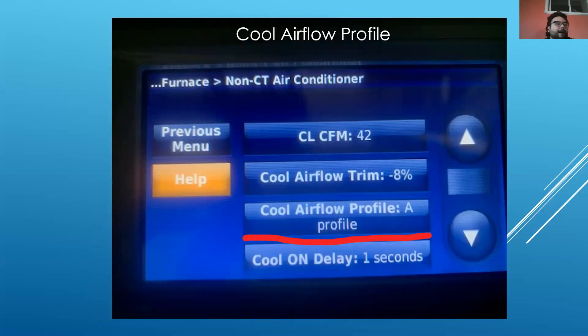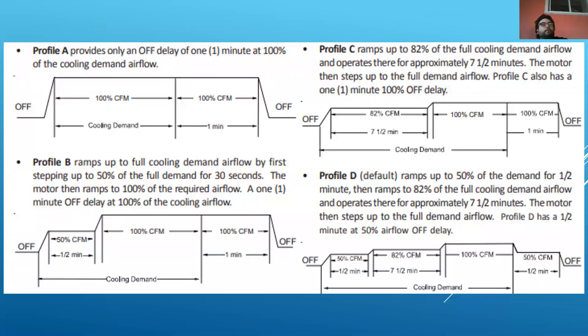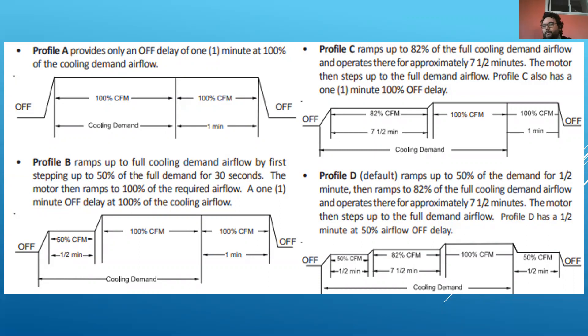We can also set profiles, which control the actual ramping up and down of the fan during a cooling call. Profile A ramps up to 100% of demand right away — no attempt to dehumidify with a lower fan speed. This might work for customers who want immediate airflow or for certain zoning systems. Profile B runs at 50% operation for half a minute, giving extra dehumidification by getting the coil really cold to pull moisture out of the air. Profile C ramps up to 82% right away for about seven and a half minutes, then bumps to 100% if not satisfied — that's pretty good for dehumidification.